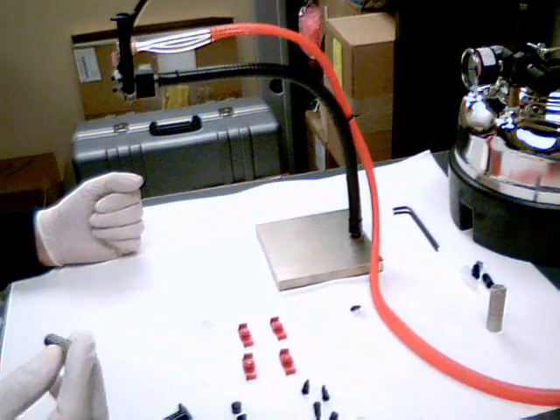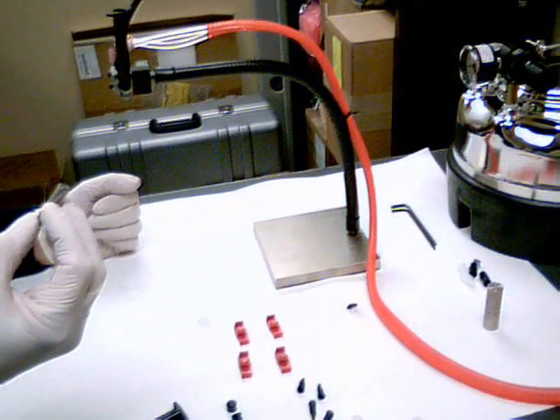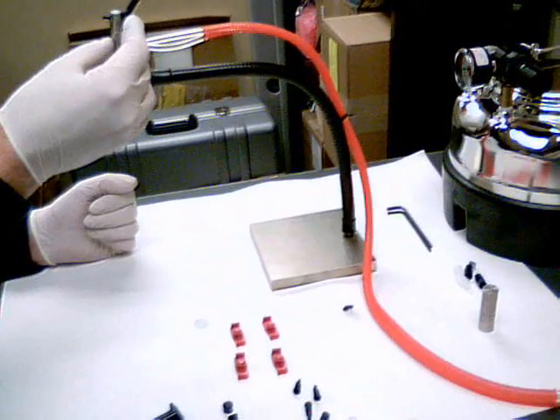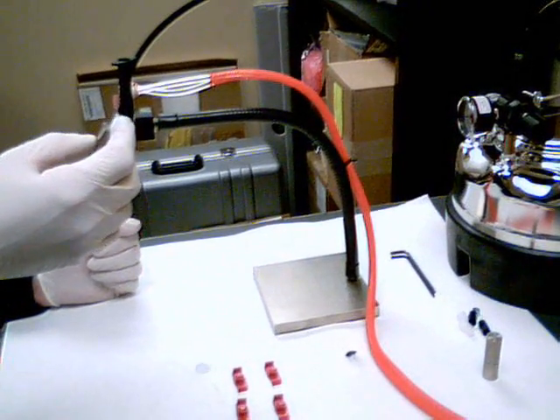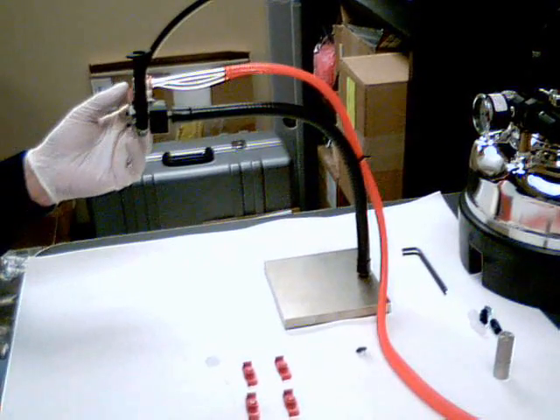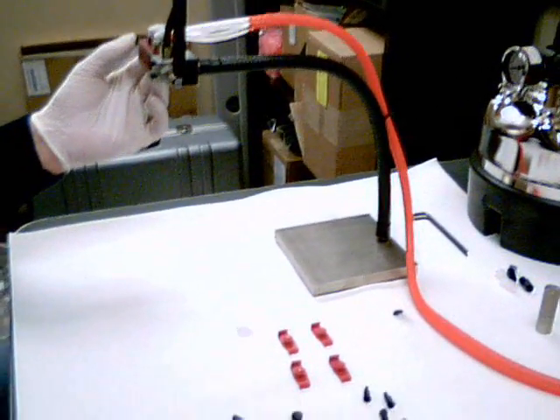During that process, I have a gauge tool that has a line on it that tells me when my piston is in the right location and my syringe is full. I'm going to insert this into the syringe and pre-fill until my gauge comes up to the fill line, and I'll stop at that point.